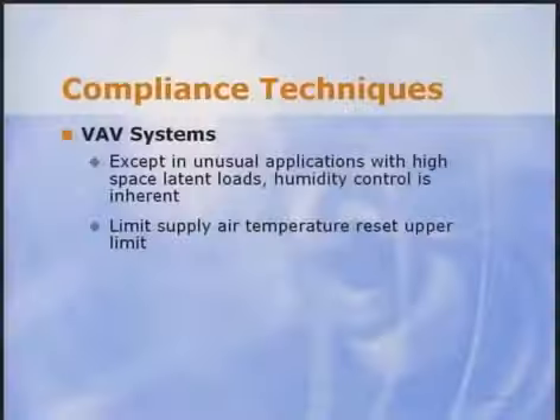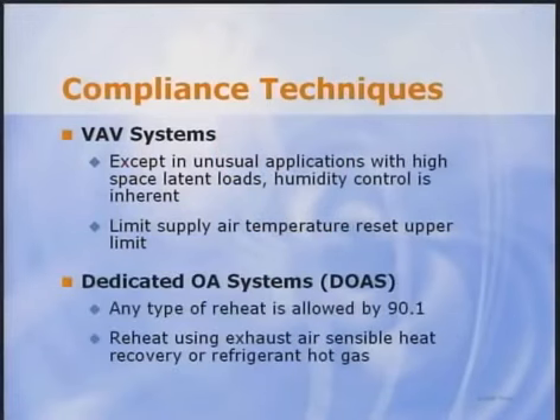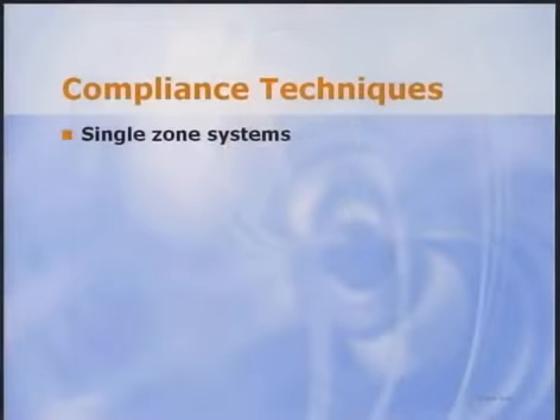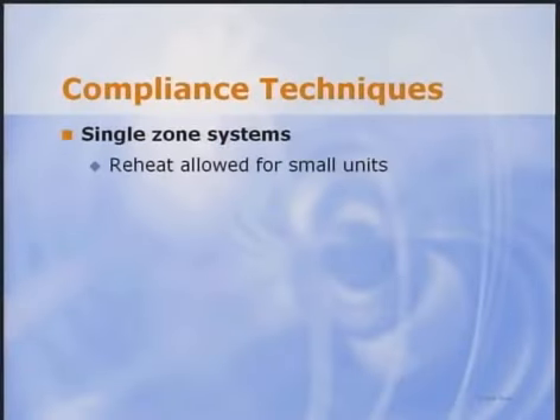Compliance with 90.1 for dedicated outdoor air systems is also easy. You can dehumidify pretty much without limitation since 90.1 allows reheat of the entire design minimum outdoor air rate. However, efficiency can be improved by reheating with heat recovered from the exhaust air stream or, for DX systems, by hot gas from the cooling system. 90.1 also offers many exceptions to allow reheat for humidity control with single-zone systems. First, as Mick showed, small systems are exempted and may use any type of reheat. Again, efficiency can be improved by using hot gas, coil bypass, and sensible heat recovery, but they're not required.